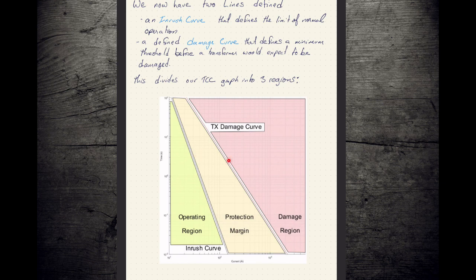And what you get is this margin in between. And if we can drop a fuse that fits in between here, then we can interrupt the flow of electricity only when it's above the inrush, but while it stays below the transformer damage curve. And this is kind of what we're hoping to achieve. We don't want our fuse to operate when we're in our normal region, and we want our fuse to finish operating before we cook our transformer. And so what we want to do is pick a fuse that rides in between these lines and protects our assets without causing nuisance trips and leaving our customers in the dark for nothing, and without allowing our transformer to blow itself up.